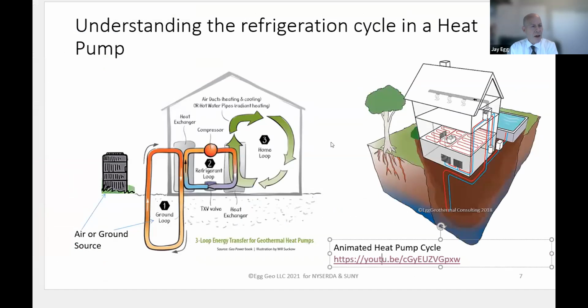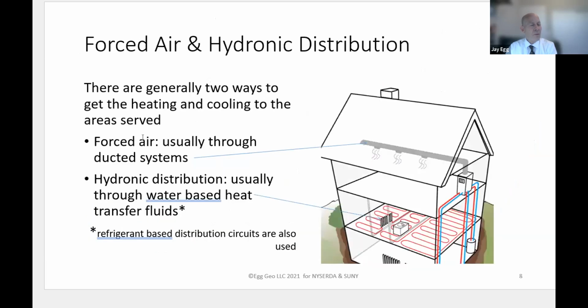So this heat pump device, which is indicated here, uses energy from underground, compresses and intensifies it, and it can be used for radiant floors, for radiators, for water heating, for pool heating, and it can use very low intensity heat, easily as low as 5 degrees Celsius. If you have 5 degrees Celsius underground, it can create all the heat you need for domestic hot water, for heating, and for cooling.